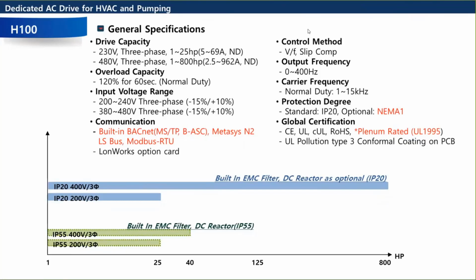So I see some other questions coming up. So Ethernet, we are working on an Ethernet module for the H100. The main reason we're working on that is because we're going to do a lot of utilities or municipal applications, and those guys are using Ethernet to connect to their SCADA. So we are working on an Ethernet IP option card. The ones that are listed in red here are actually the standard ones. So BACnet is built in, Metasys is built in, Modbus RTU is built in. It's just a parameter to change what protocol you're using. Option cards, we have the LonWorks card. Not too common, but it's there. Then we are working on the Ethernet IP card. So yeah, that's a good question. And the cards that we make are selectable for Ethernet and Modbus TCP. So it's the same card all in one. You just flip a dip switch.